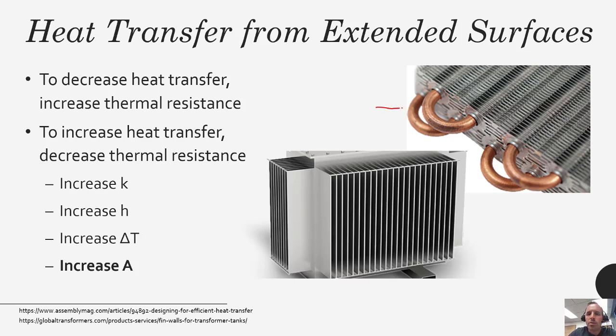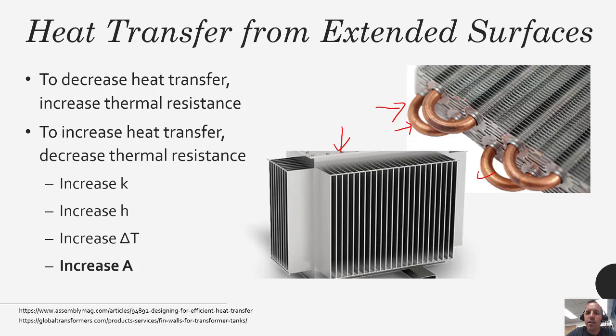I'm showing here a couple of examples of how you might increase the surface area. There is a heat exchanger on the right, so that heat exchanger is carrying some kind of fluid through these tubes and it's likely a liquid on the inside exchanging heat with a gas going through. Having all these extra fins and extra surface area is going to give you a higher area, so by Newton's law of cooling — Q equals H A delta T — by increasing that area you certainly increase the total amount of heat transfer.